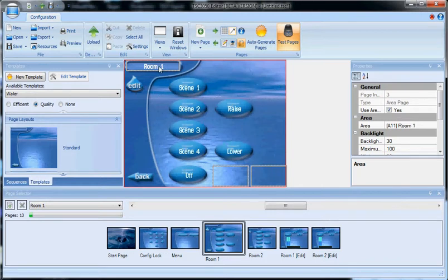So the next thing we want to do is upload this to the touchscreen. Now we can either use TSC30 or TSC50. I've got a TSC50 attached here, but the only difference is the way that it selects the COM port for the USB. The other thing with the TSC50 is to disconnect the CAN cable from the back if there's other traffic on the network, because this can sometimes slow down the upload. So we just click on upload.